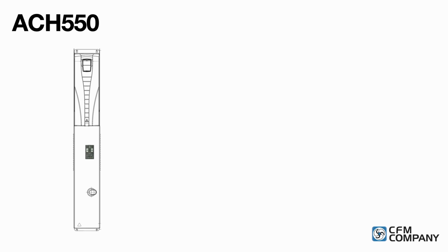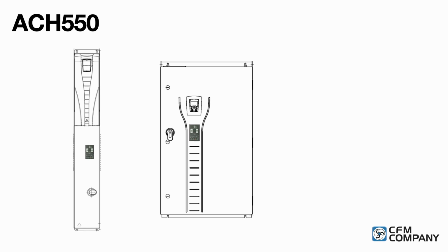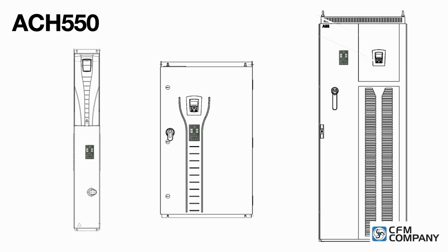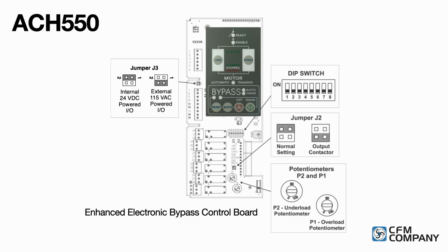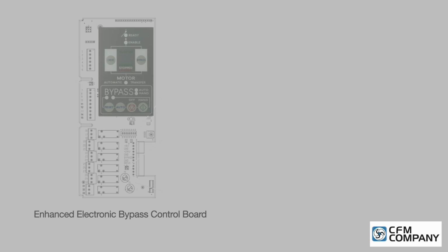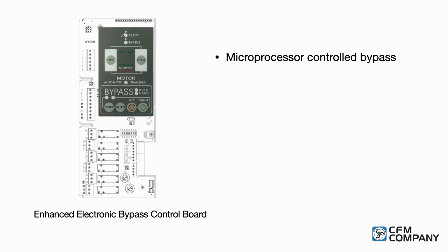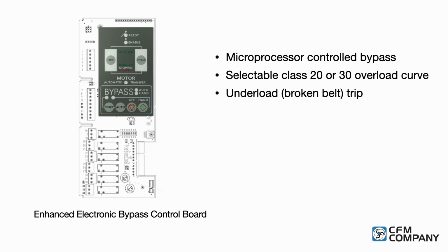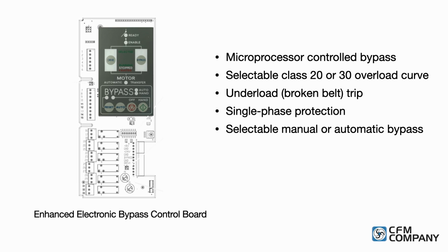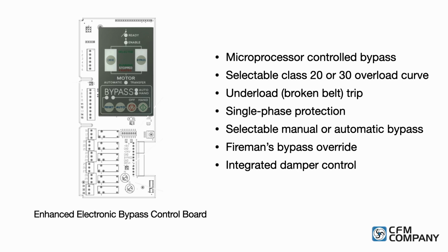In 2003, ABB introduced the ACH550 drive and continued to offer the Enhanced Electronic Bypass. For the era, the electronic bypass offered industry-leading standards that are still in use today. Features such as microprocessor-controlled bypass, selectable class 20 or 30 overload curve, underload broken belt trip, single-phase protection, selectable manual or automatic bypass, fireman's bypass override, integrated damper control, multi-voltage power supply, and many other features.